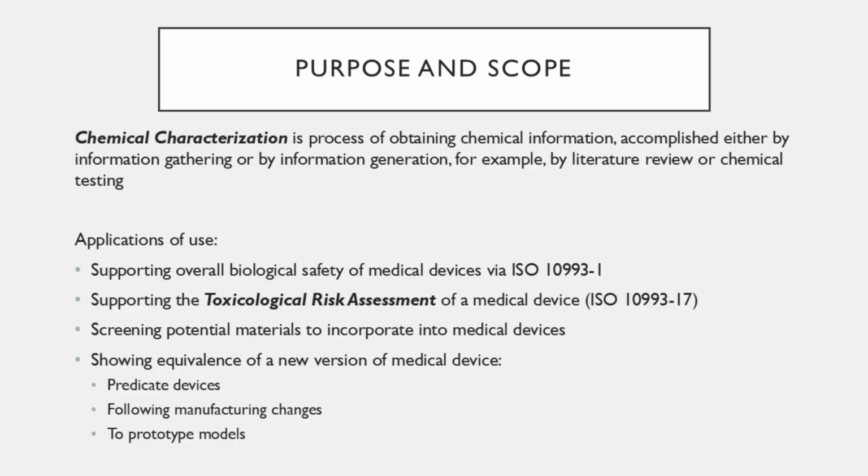So very often as you change or tinker or optimize a medical device, you might relook into chemical characterization to understand how any of the changes you implemented change the overall chemical profile and therefore the toxicological risk or TRA profile of your medical device.